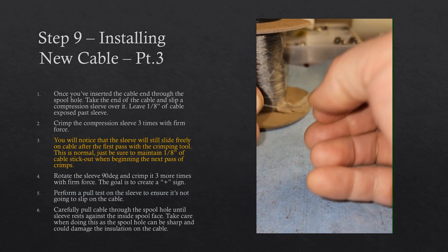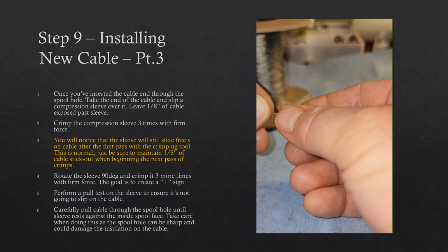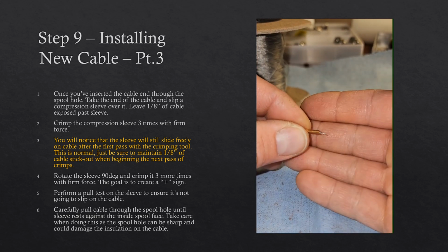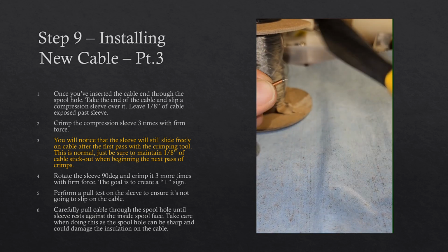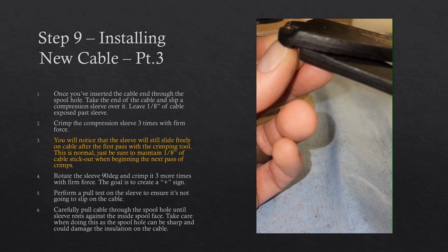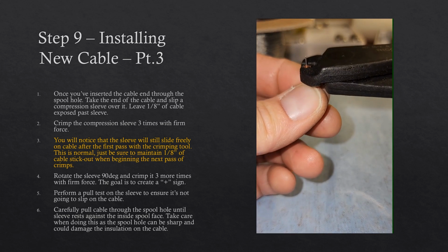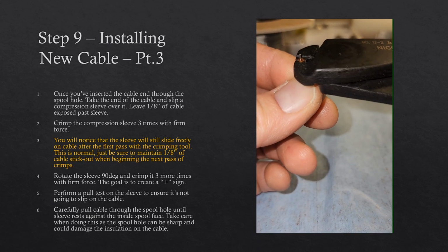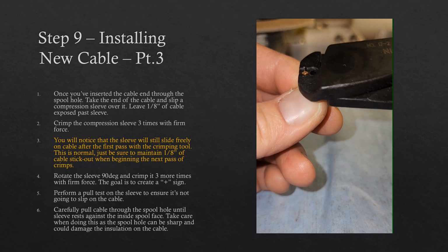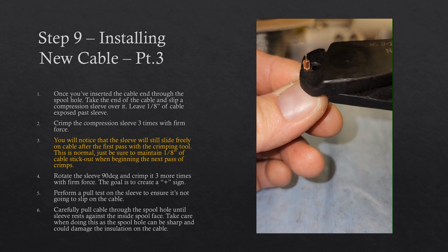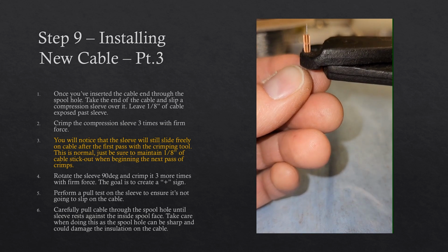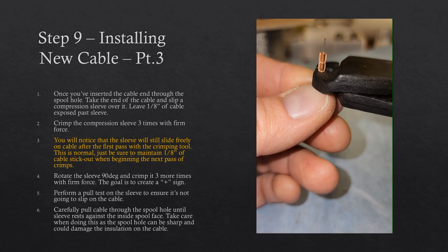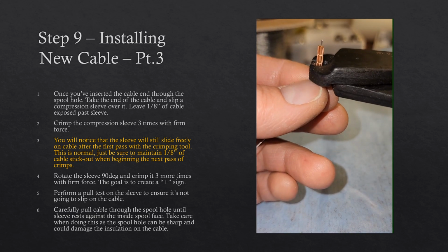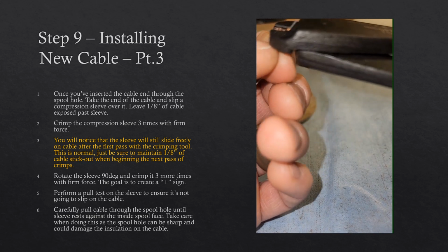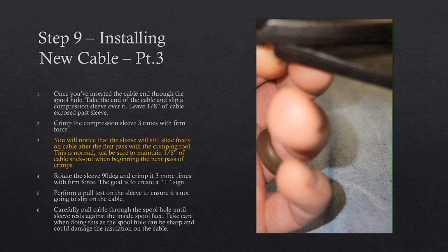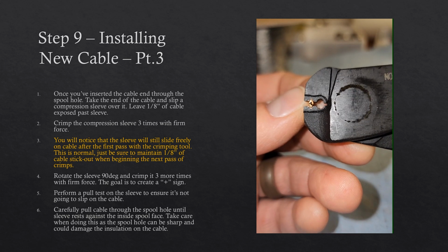Once you get the cable through the spool, you're going to install another copper sleeve onto the end of that cable. You want about an 1/8 inch or so of the cable sticking past the sleeve. And again, you're going to compress 3 times down the length of the sleeve. Use a fair bit more force when doing this one. We don't have to worry about a rubber bushing, so I like to make sure we grip it nice and tight. And what you'll notice is even after the first pass that cable is still sliding around inside of the sleeve. That's fine. It's normal.